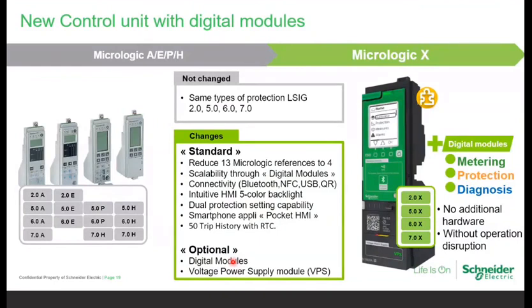Thank you so much. So let's say I have selected the MTZ ACB with 6.0x release, and if tomorrow you want, let's say, under frequency and over frequency protection in your ACB, you can just go and buy an under frequency over frequency digital module from the Go Digital website for a cost of 10-15,000 or 5,000, and you can install that in the ACB. Then we have a VPS, voltage power supply, which is an optional module. If you select the 7.0x, which is LSIV, that is earth leakage protection, then VPS comes by default. Moving to the next slide.